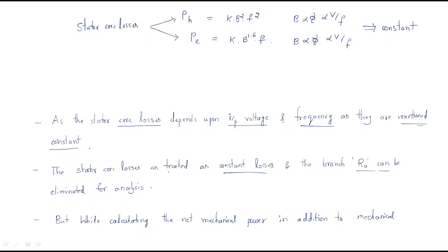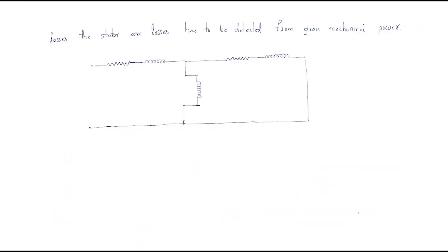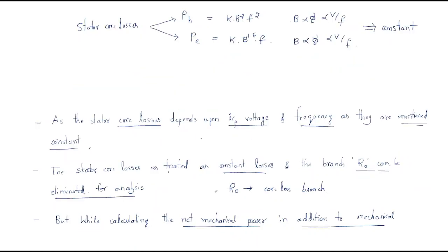Since these stator core losses are constant, the R0 branch can be eliminated for the analysis. There is no variation, so we can remove this branch. R0 represents the core loss branch, but when calculating the net mechanical power, the stator losses are also considered and must be deducted from the gross mechanical power developed. When considering all losses we will account for this, so the modified circuit simply removes R0.